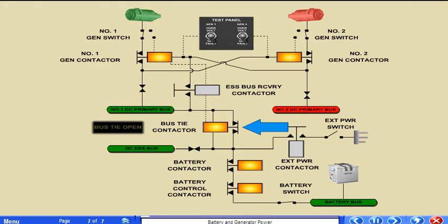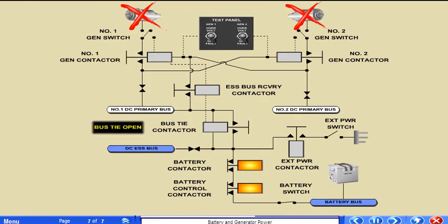The bus tie contactor activates automatically whenever either generator or external power is available to supply power to the essential DC bus. Another primary function of the bus tie contactor is to isolate the battery from the DC primary buses in the event that both generators fail. If this occurs, the bus tie contactor is open, illuminating the bus tie open caution message. The only buses powered will be the DC essential and battery buses for as long as the charge of the battery lasts.